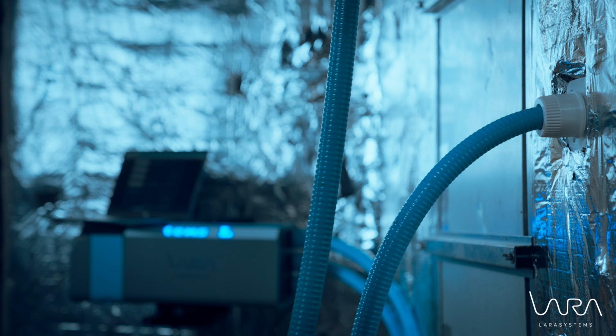When selecting the installation points, one of the most important rules is that the injected disinfectant liquid must not come into direct contact with the sound damper. Therefore, the heads must be installed on a section where the vaporized disinfectant is allowed to enter the supply airflow without obstruction. Once we have determined the appropriate supply point and ensured that it is located after the sound damper, on a suitable airflow section, we can move on to the physical installation.